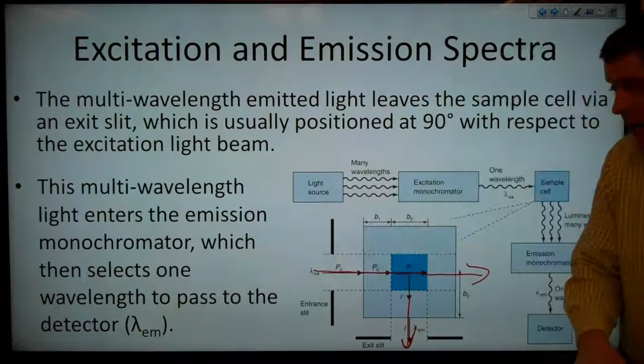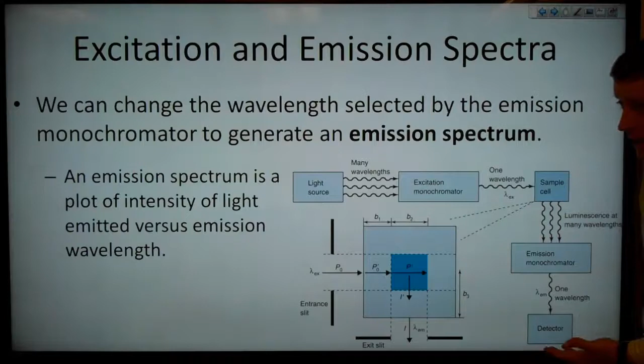So this is the lambda EM, or emission wavelength. And we can then change the wavelength selected by the emission monochromator to generate an emission spectrum. An emission spectrum is a plot of intensity of light versus emission wavelength. But we can also measure an excitation spectrum by measuring the intensity of light emitted as we vary the excitation wavelength. So in that case, we're keeping the emission wavelength constant and monitoring the irradiance coming out of the sample as a function of the excitation wavelength going in.